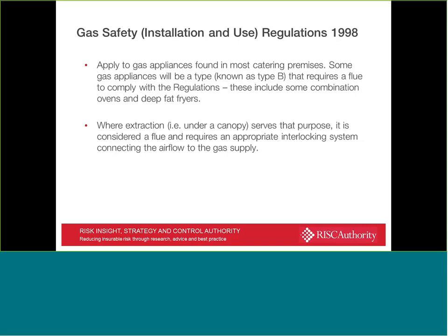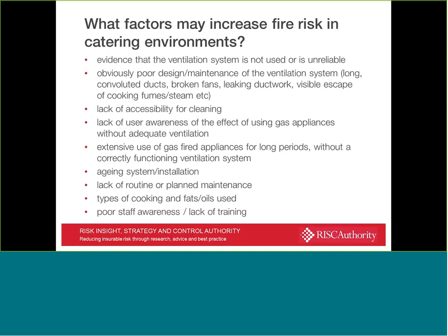However, where you do have those types of systems beneath a canopy, you should be expecting to see an interlock system which ensures that the ventilation system must be operating before the gas can be supplied to the cooking equipment itself. So moving beyond the legislation, and apologies for moving on so quickly, but hopefully you all understand the reasons for it.